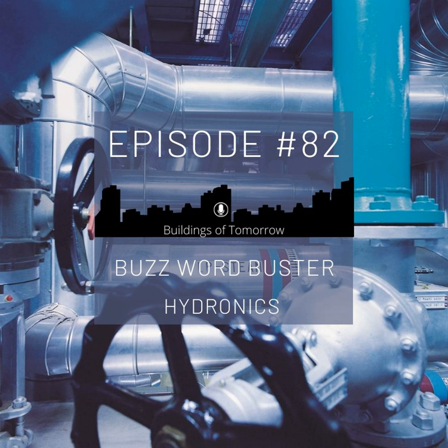So we need variable speed pumps, and I think the only thing that we have to keep in mind, unfortunately, is that we cannot control them between 0 and 100% of volume flow. We can only drive them down maybe to about 30 or 25% of the maximum flow. Below that, we cannot go further down because of the way the EC motors and the variable speed drives are designed and work.